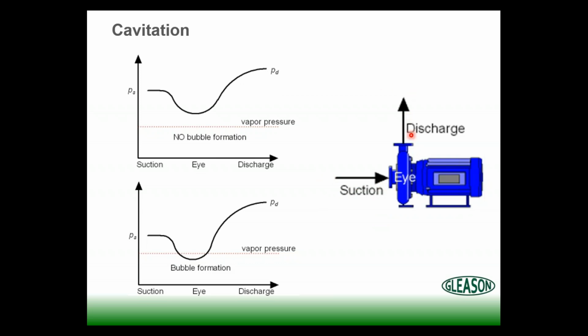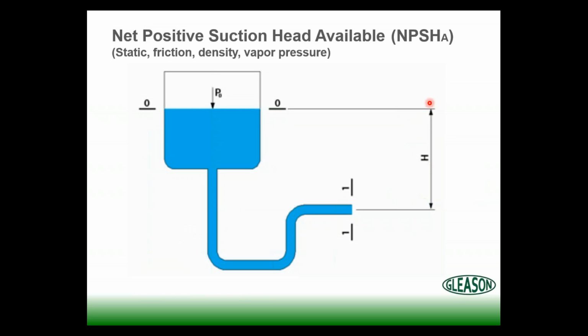So now we have a mixture of steam bubbles and very hot condensate here. Well, we can't allow those bubbles to form. So what do we do? We have to keep a certain amount of liquid head. Let's say right here is our pump suction.